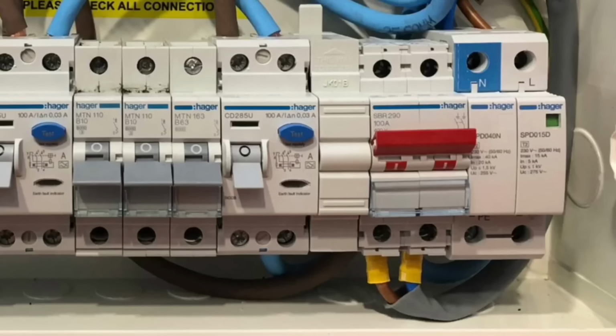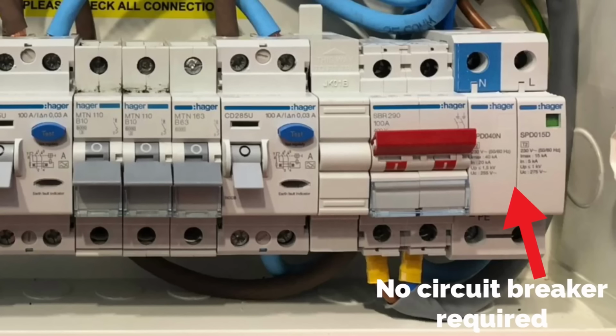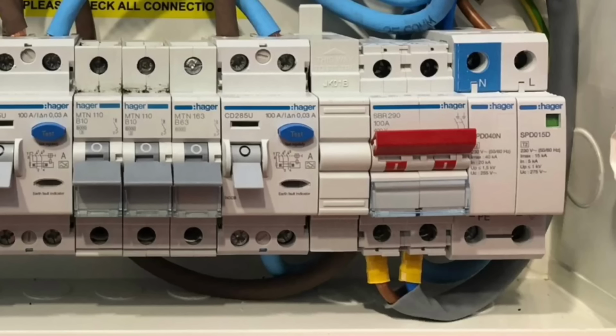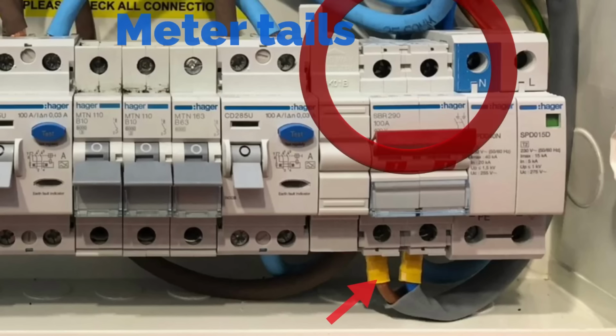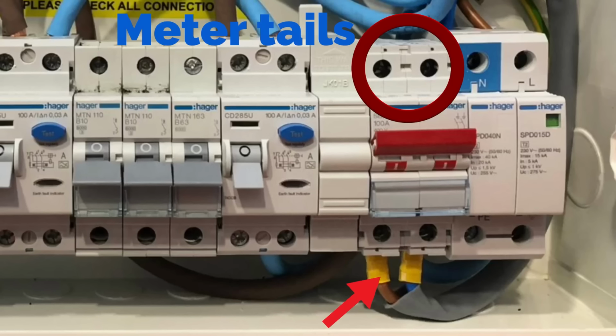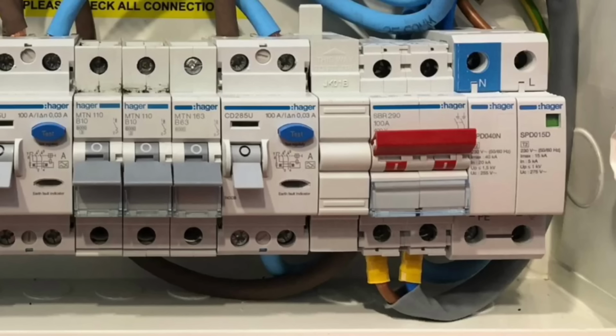So Paul, it looks here like this doesn't have a circuit protective device on it. There's no circuit breaker on here. Is that necessary? Not with this device actually. Some manufacturers require it, some don't, because there's internal protection in this particular surge protection device. So it is a parallel device. It's not carrying current. It's literally sitting across the line and earth, and as a spike comes into the installation, which could go through the equipment and damage your electronic equipment in your house, this will momentarily switch down to earth, extremely fast, of course, and dissipate that surge to earth rather than it going through the installation.